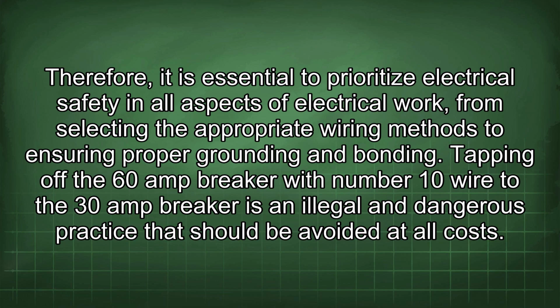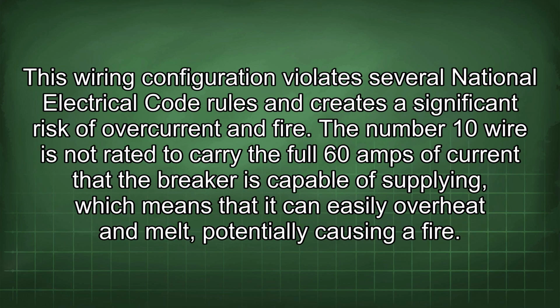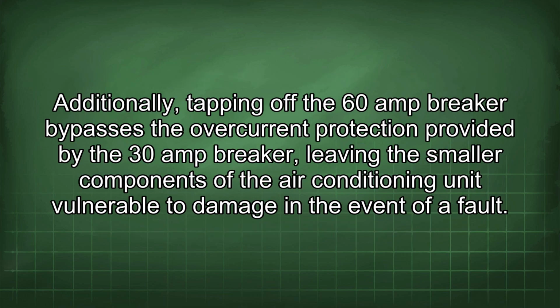Tapping off the 60-amp breaker with number 10 wire to the 30-amp breaker is an illegal and dangerous practice that should be avoided at all costs. This wiring configuration violates several National Electrical Code rules and creates a significant risk of overcurrent and fire. The number 10 wire is not rated to carry the full 60 amps of current that the breaker is capable of supplying, which means that it can easily overheat and melt, potentially causing a fire. Additionally, tapping off the 60-amp breaker bypasses the overcurrent protection provided by the 30-amp breaker, leaving the smaller components of the air conditioning unit vulnerable to damage in the event of a fault.